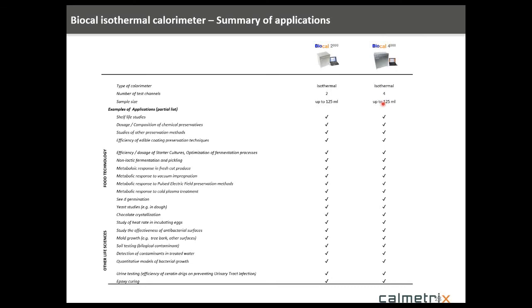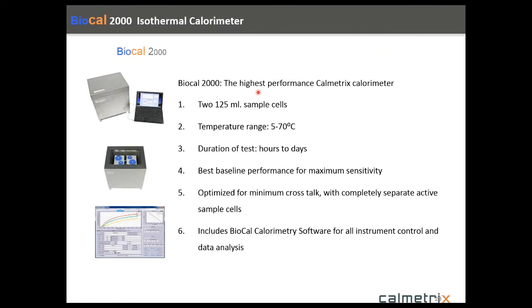There are other differences. The 2000 is really considered our highest performance calorimeter. It uses the 125 milliliter sample cells. The sample cups are the same between the 2 different instruments. There's no difference there. Temperature range of 5 to 70, again, that's the same between the 2 instruments. The duration of test here I've indicated as hours to days. Most of the experiments that we do might be 24, 70, 48, 72 hours, 2 to 3 days, but it doesn't preclude you from running 30, 40, 50 days. It really just depends on the application and what you're trying to measure. And both instruments can run in those modes.